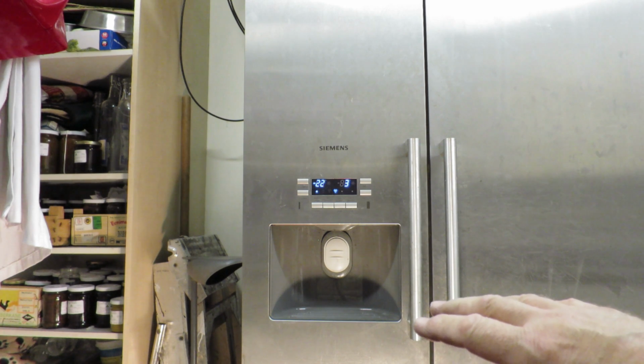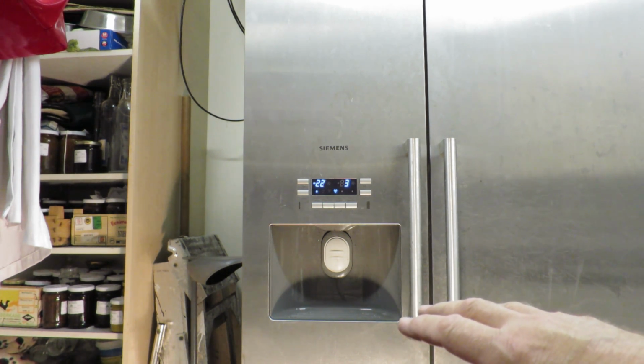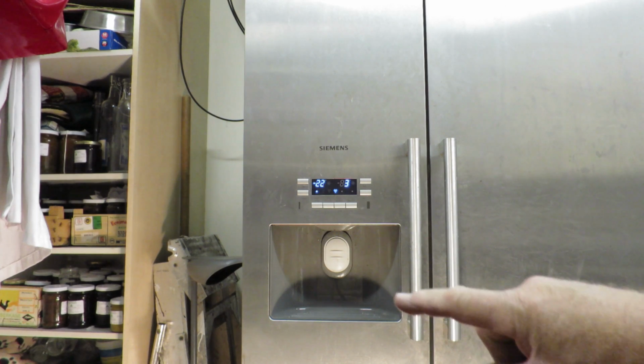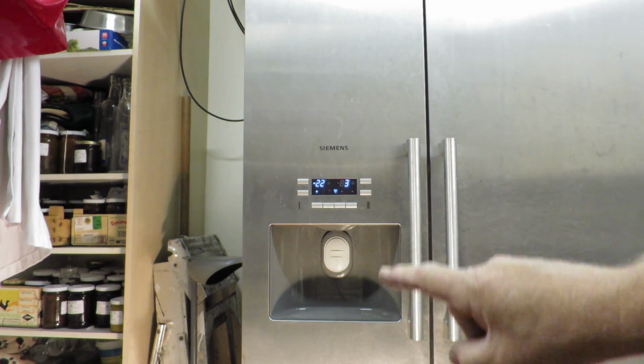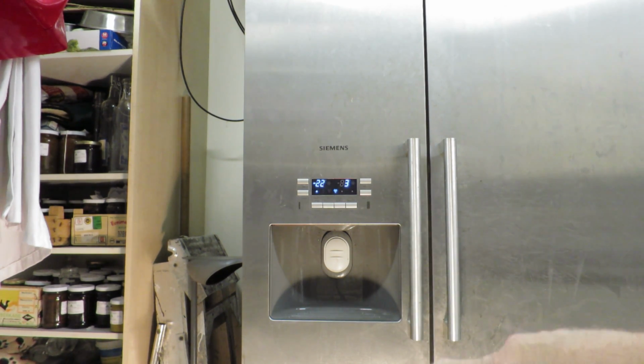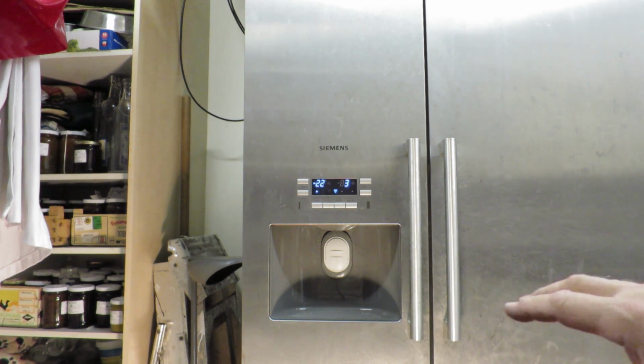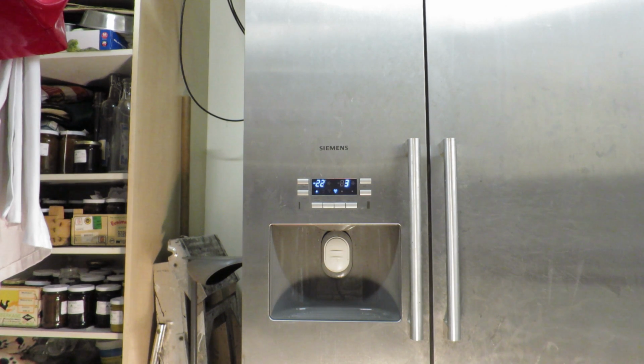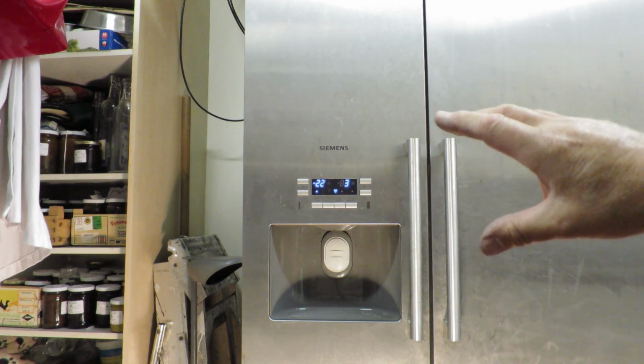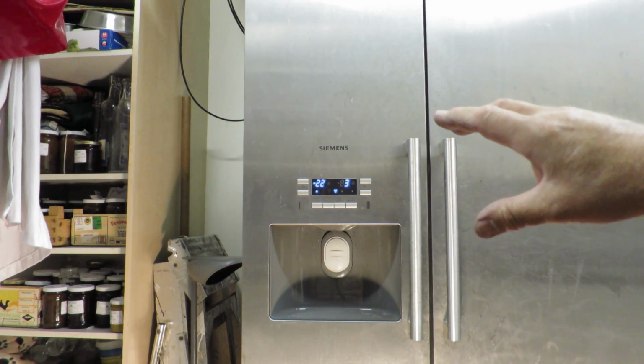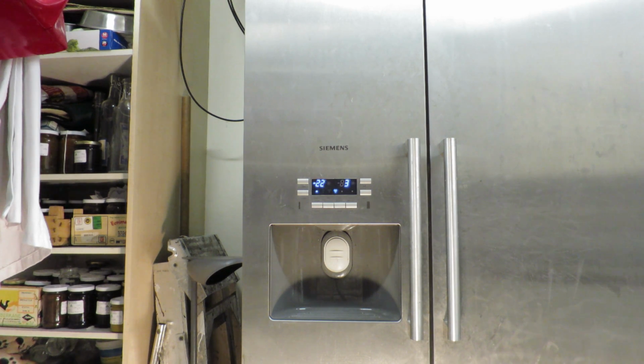I think the main cause of my icing up - the other symptom of course is I had ice coming out, had water coming out of the bottom, and that's because the drain hole did ice up. I think the main cause was not any of the sensors or the heater, it was the fact that the fan was not circulating the cold air around, and then when it went on to its heat cycle it was not pulling the hot air up through the cooling coils and fins, and ice was forming at the top end.